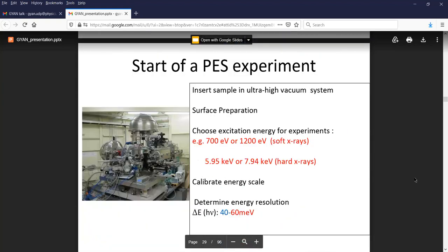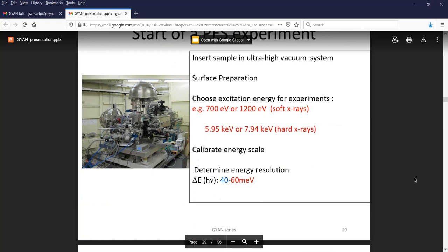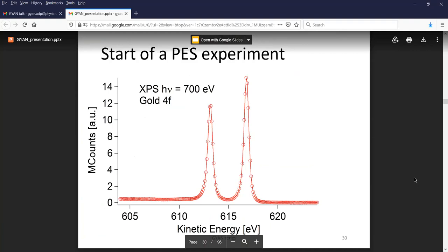A typical experiment means you insert the sample, prepare the surface, choose the photon energy, and calibrate the energy scale to determine energy resolution. You can measure a reference sample, which is normally gold, and depending on the binding energy or kinetic energy that you measure, estimate the binding energy and calibrate your energy scale.